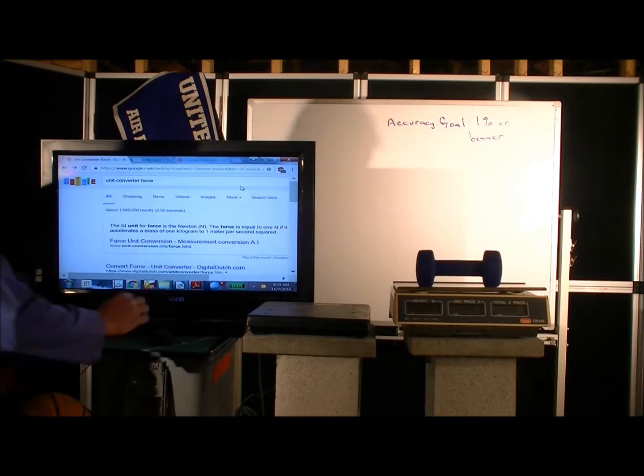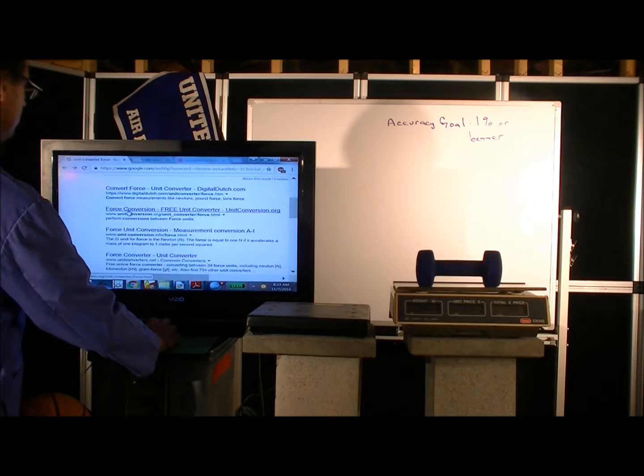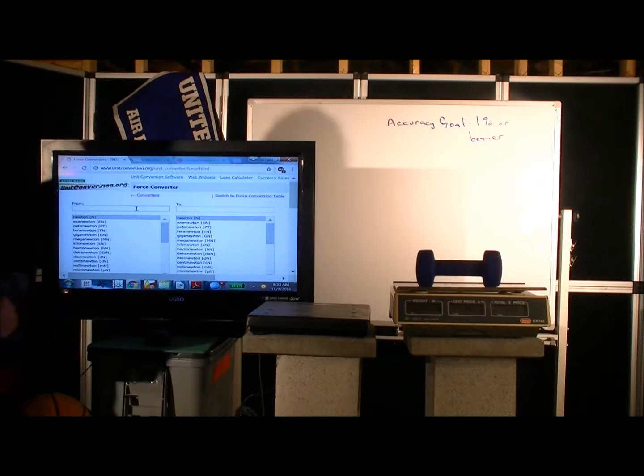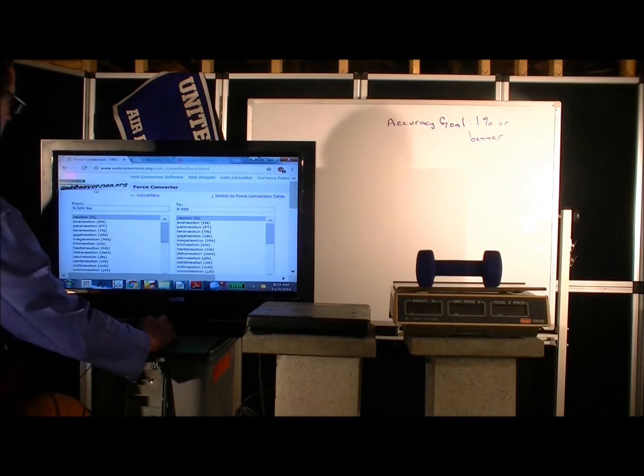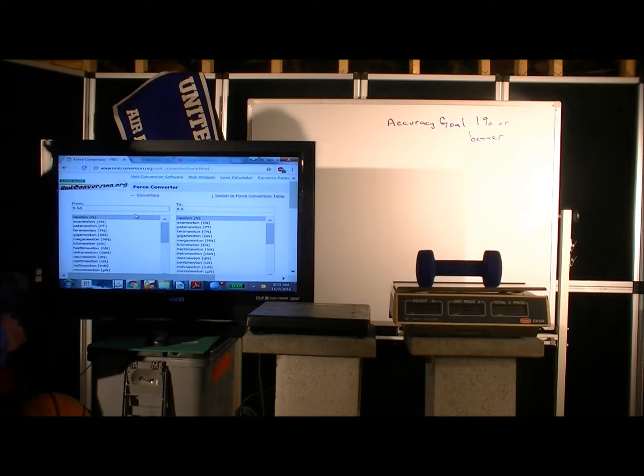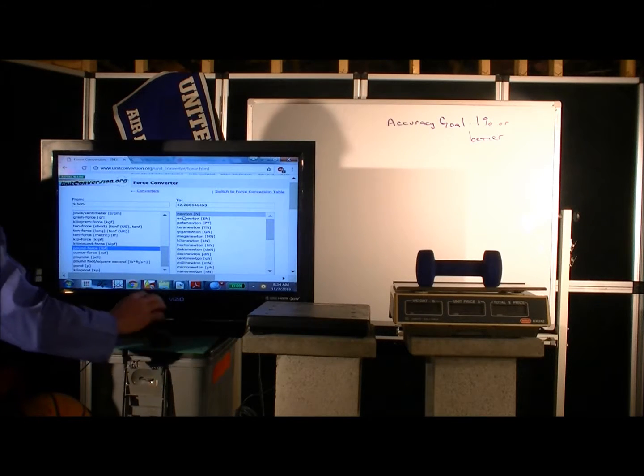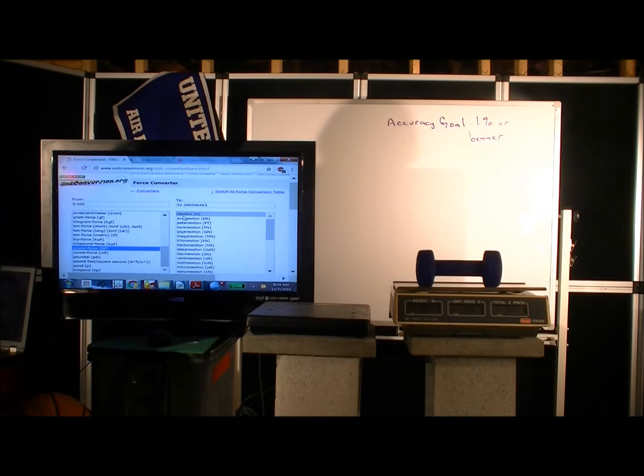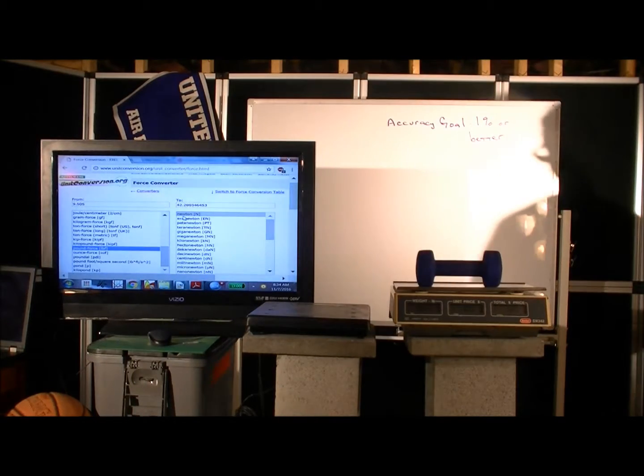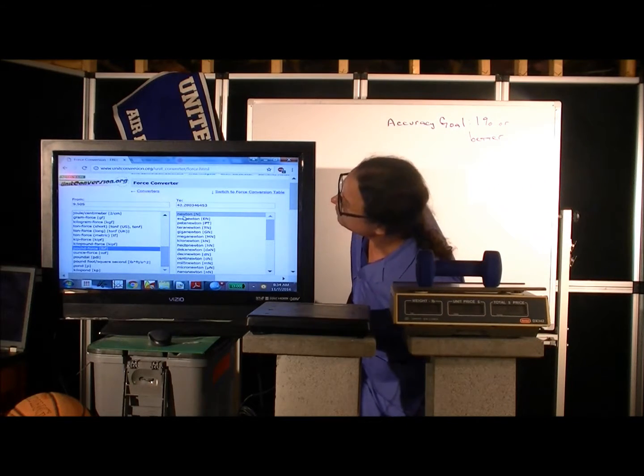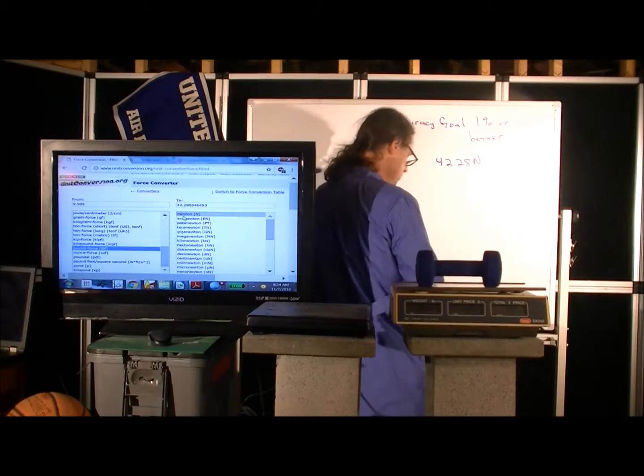So we come to Google and we Google up a unit converter for force, and it gives us several options. And this is unitconversion.org, which is one I've used a lot. And so let's just convert 9.505 pounds. Let's see, it might want us to scroll down and select pounds here. 9.505, scroll down to pounds, converted to Newtons. So 9.505 pounds is 42.28 Newtons. So let's just write this down because we're going to use this. See what the number was again: 42.28 Newtons. We're going to use this to double check the accuracy of our force plate.